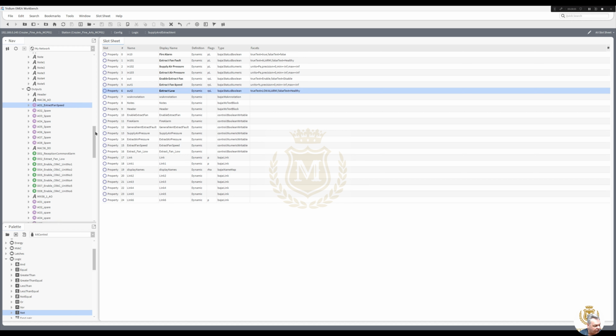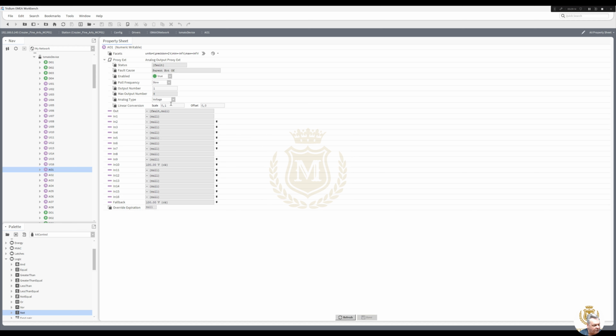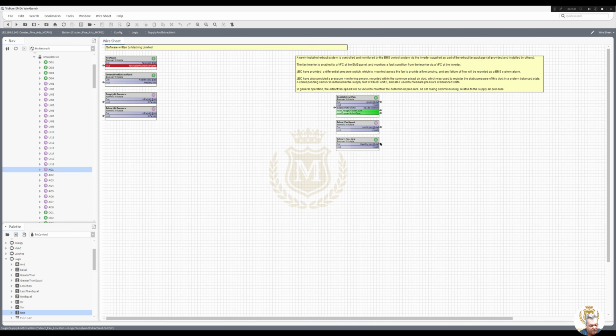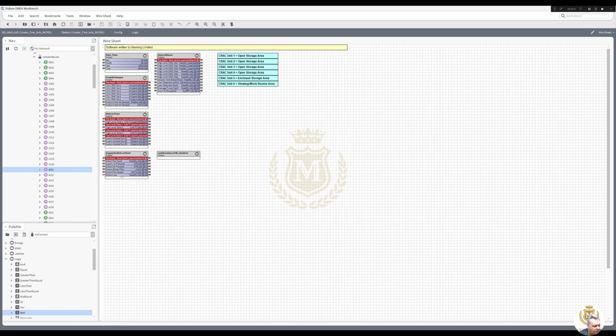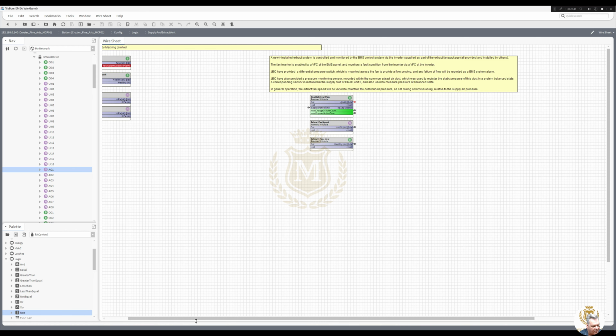Now we're going to be doing the fan speed 0 to 10. I think I've already changed the point, but I'm just going to check the point for AO1 to make sure, because it normally accepts 0 to 10 and we're doing 0 to 100, so we need to move it across by 1 decimal place. Yeah, I've moved it across. So normally that's at a 1, so 0 to 10, and I'm doing 0 to 100, so it's easier just to move the decimal place and put in a conversion in it. Save. So now all the points are linked up, all the inputs and the outputs here. It's not giving the speed at the moment, so now we've got to write some logic to go in between there.